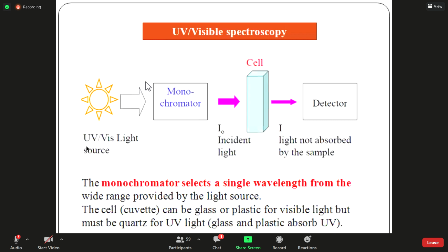Then this is a monochromator. Do you know what a monochromator is? Single wavelength light. Yes, it allows only one wavelength to pass through it. Exactly. Why do we need only one wavelength? Because we have to pass light of a particular wavelength through the material, where we get the maximum absorption. So we cannot use polychromatic light. We have to convert it into monochromatic light. The thing that converts polychromatic light into monochromatic light is known as a monochromator. Inside the monochromator, there is a prism by which the rays are diffracted.